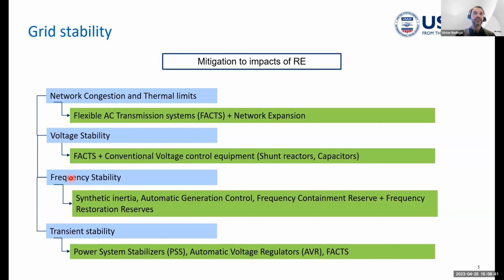For transient stability, we need to adjust different technologies for power system stabilizers, and also automatic voltage regulators, basically to improve energy security in the system, and avoid issues when we have large integration and interconnection with larger systems, such as power system oscillations and that kind of stuff. So these are different technologies that are impacting RE integration into the network and improving the different situations we are having with RE integration.